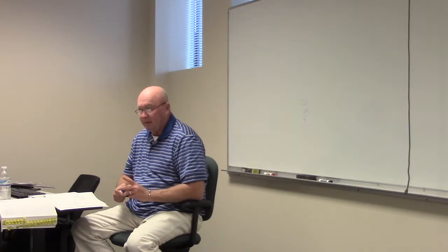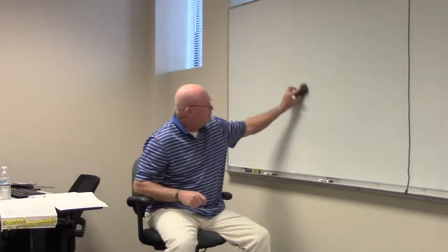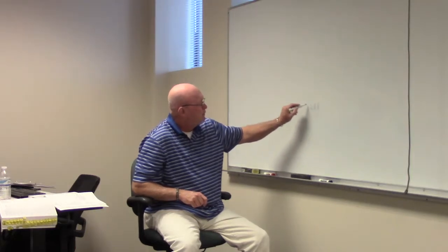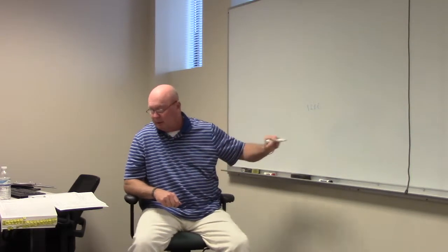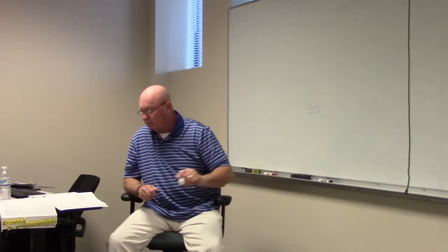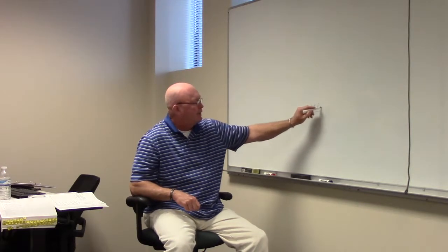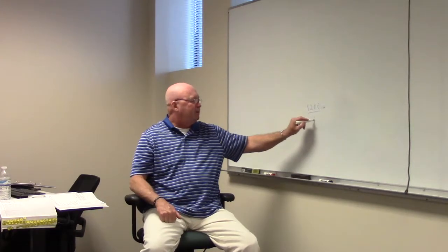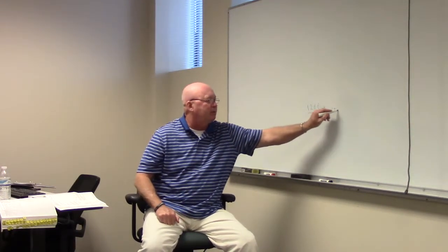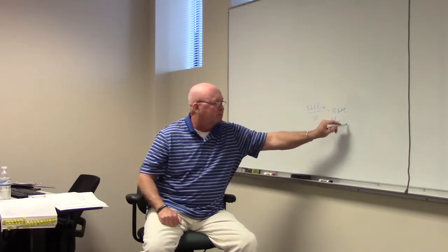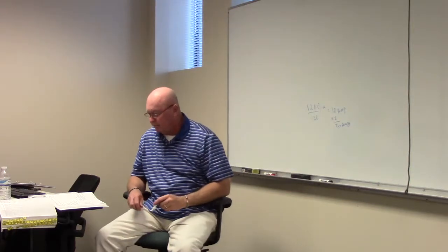Okay. Now, how many sign circuits are there? 2. How much is a sign circuit? Minimum has to be what? 1200. All right. So we got to get this to amps though to be able to get it in our sample. So this is volt amps, right? Yes. So to get to amps, what are we going to do? Divided by volts. Divided by volts, which is 120, and that's 10 amps, right? Mm-hmm. And we have 20 amps. Y'all agree with me there?